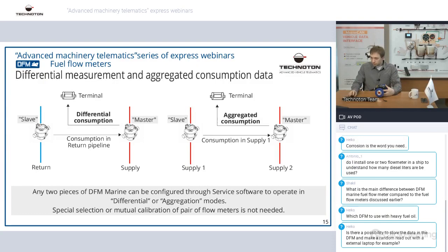On this scheme, you can see that the flow meter installed on the return line is configured as a slave. The flow meter installed on the feed line, or supply line, is configured as a master. The master is responsible for the flow rate in the feed line and also for calculating the difference between the fuel in the supply line and the fuel in the return line. So the master requests the flow meter configured as a slave to calculate the difference. Hope that's clear.